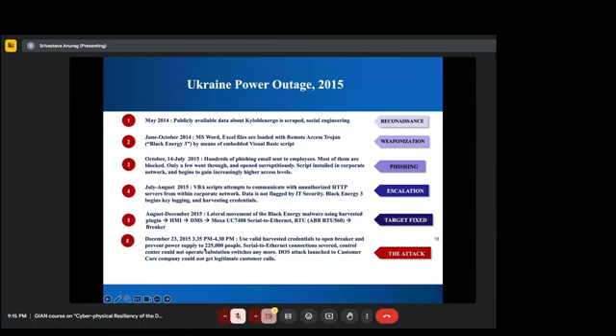From there, they were able to get into the HMI, the human machine interface, then to the DMS, distribution management system. From there, they got into the substation devices, the RTU, and from there to the breaker. Once you get to the breaker, you open multiple breakers and open the line, resulting in an outage affecting 225,000 people. So that is one example.